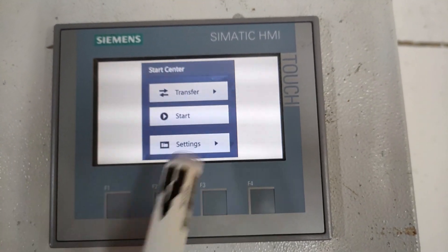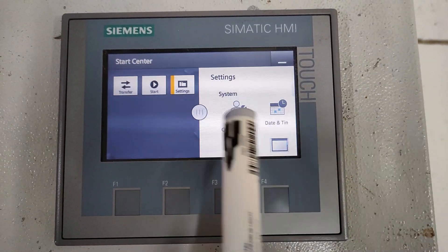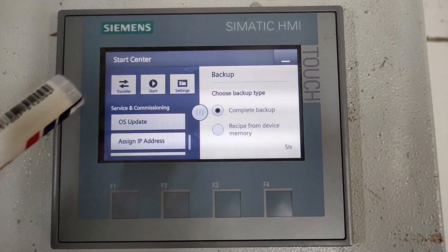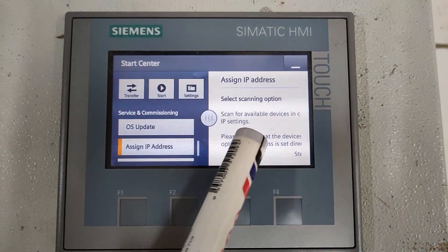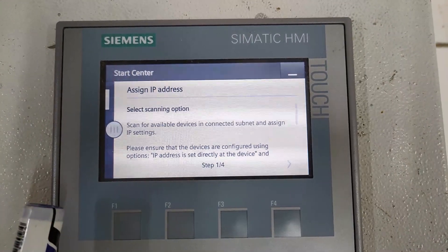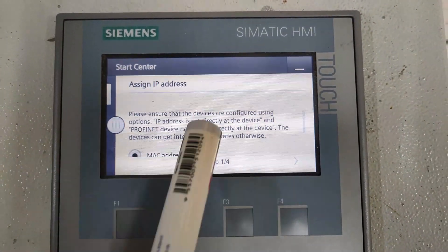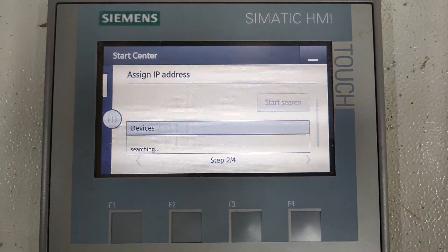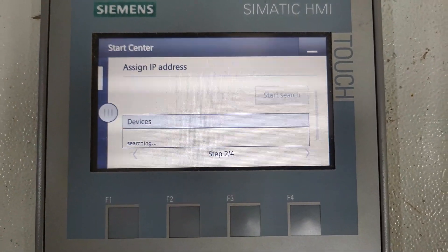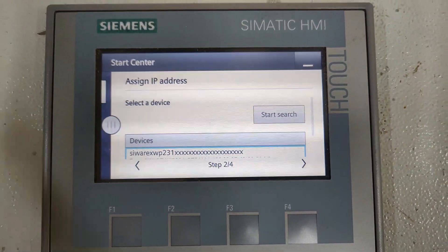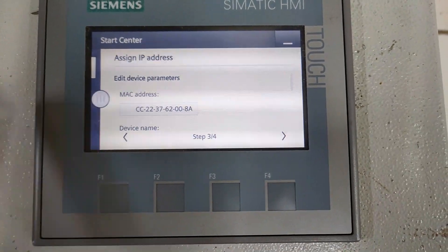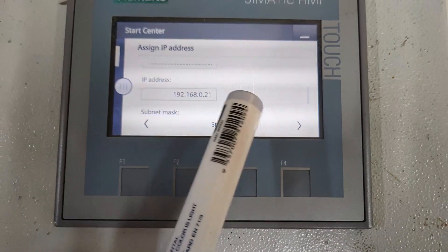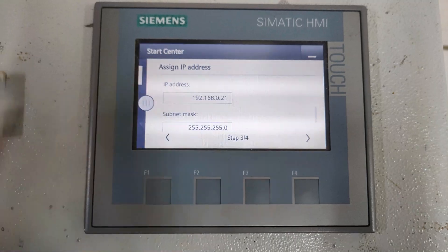Click on Settings, then click on 'Service and Commissioning,' and go up to 'Service and Commissioning.' Click on 'Assign IP Address' — it will scan for available devices on the network. It is setting the IP address directly on the device. It will show the connected devices; right now there is only one device, the WP231. Its current IP address is 192.168.0.21, and the MAC address is also displayed.